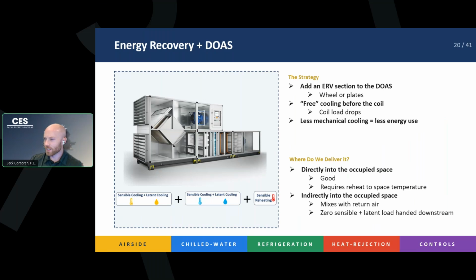And right, so those were the three systems, but what if we combined some of them? If we need a very energy efficient solution, we want to use as little cooling energy as possible, right? So if we can drop the temperature of that outside air before it even reaches the coil, let's do it. If we can combine the ERV and a DOAS unit together into one large air handler, we can get that pre-cooling with that yellow temperature right on the bottom left. We get that yellow sensible cooling, the yellow latent. And so that 95-degree air isn't 95 anymore before it hits the coil. It's 81 and a little bit less, latent driven.